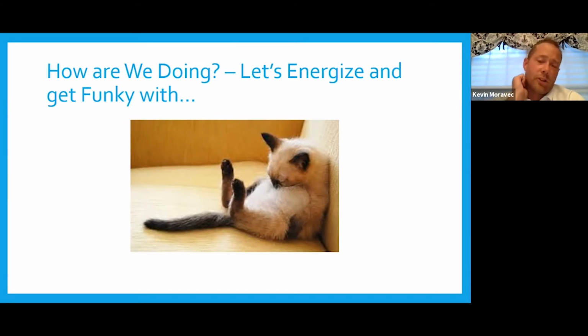What really turned us on to it was the old way of piping boilers: primary loops into secondary loops that went to distribution, and in some cases even tertiary loops coming off of those. It was a hodgepodge, because the boiler doesn't care—it'll run at 180, 190 degrees and be pretty happy.